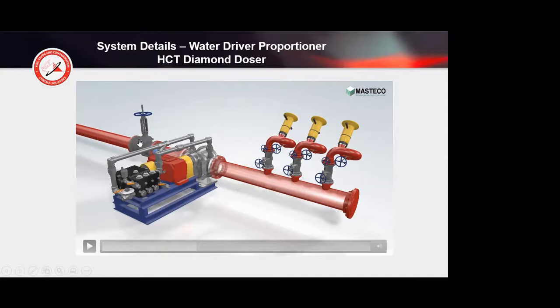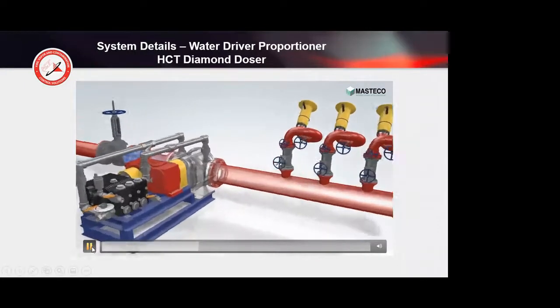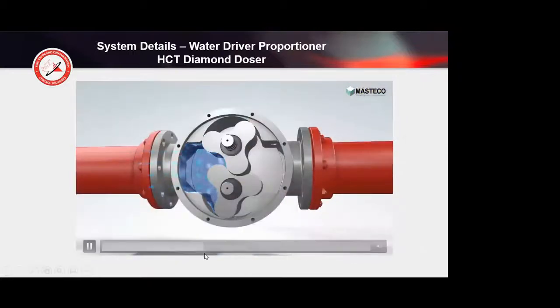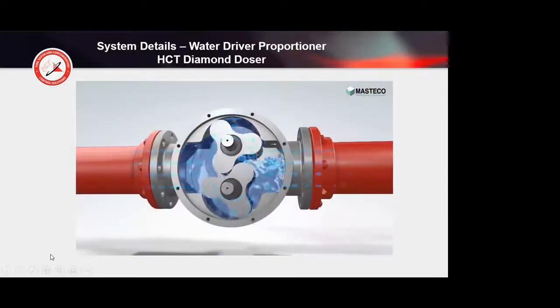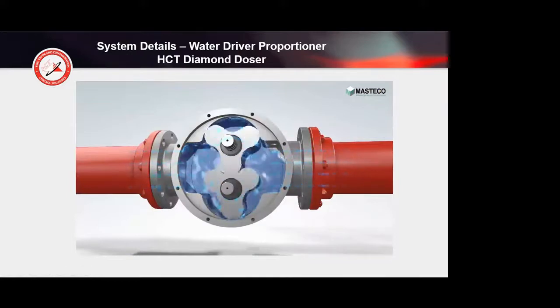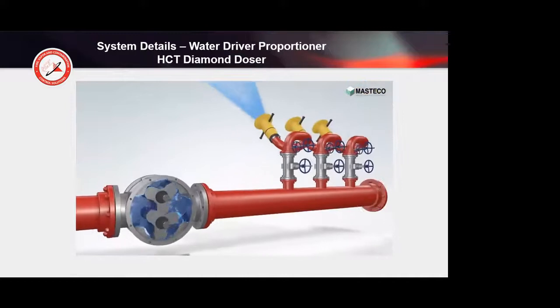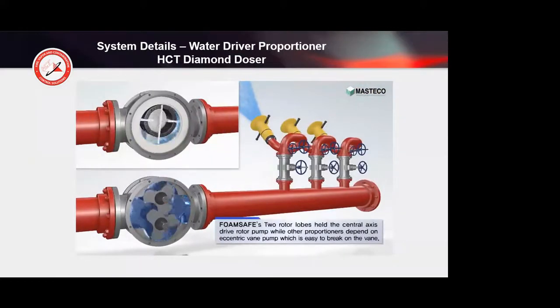So your water is going to flow through this and then up to whatever device you want to feed. You can feed a monitor, a sprinkler system, a pre-action sprinkler, or an open head deluge system. The water goes through - I like to describe this as turning the hamster wheels that are attached to a gear. The gear is pumping the pistons, bringing the solution over to whatever device you're going to deliver it to.